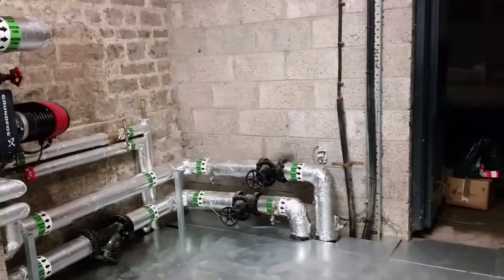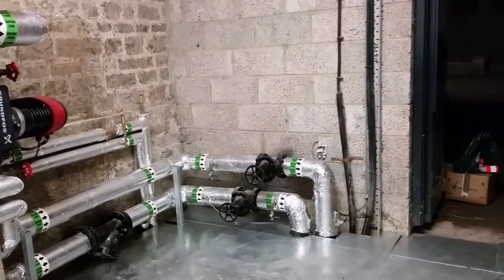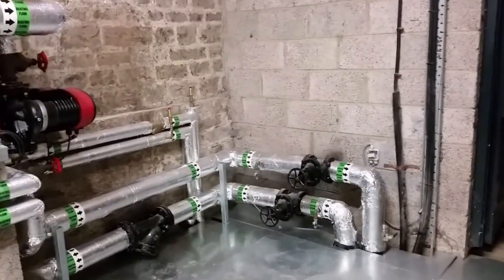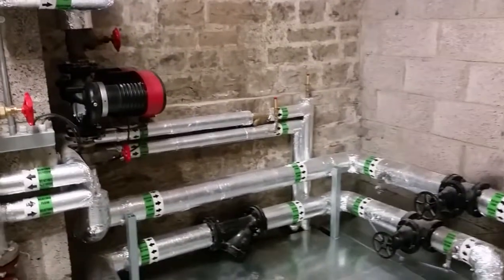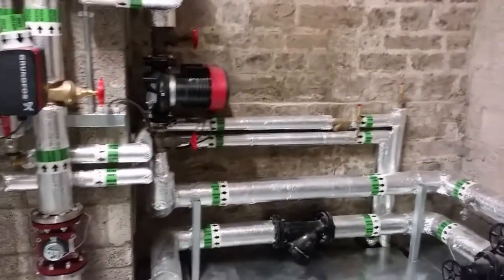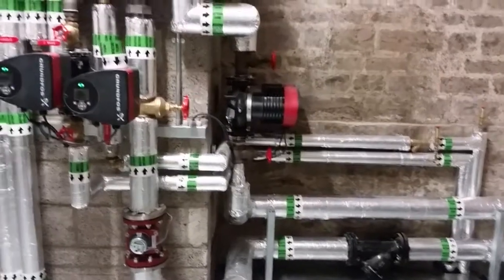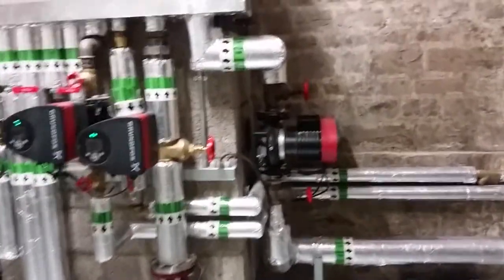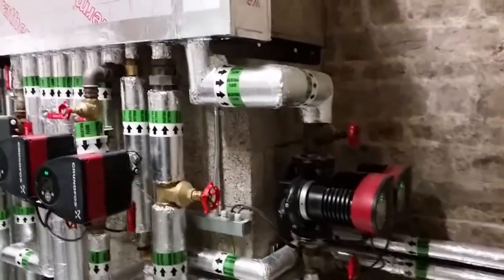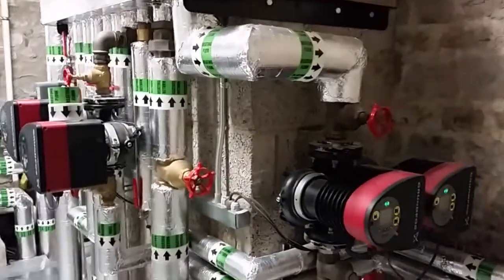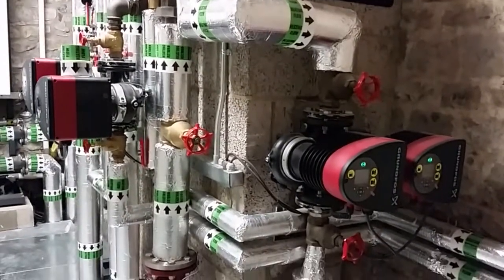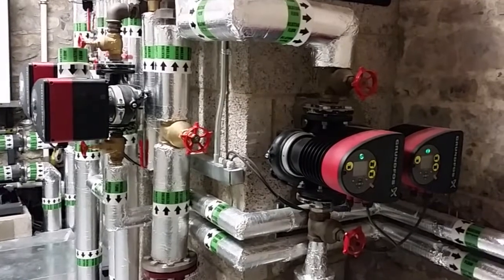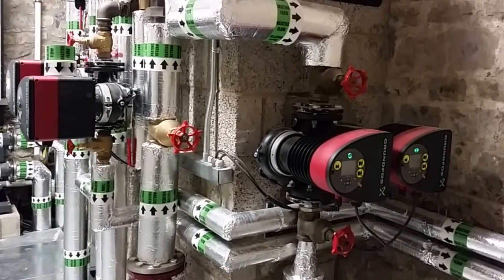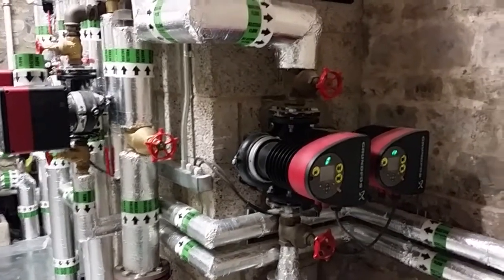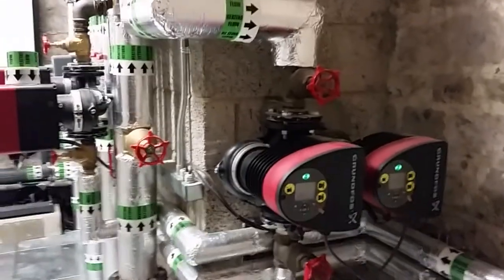The original heating system enters the boiler house through two 75mm flow and return pipes that were originally connected to two conventional oil boilers. They're now instead connected to an energy zone manifold and an energy effective Grundfos speed controlled pump. This pump can decide which is the most appropriate speed to operate at, and they can automatically change over as required if a fault crops up.